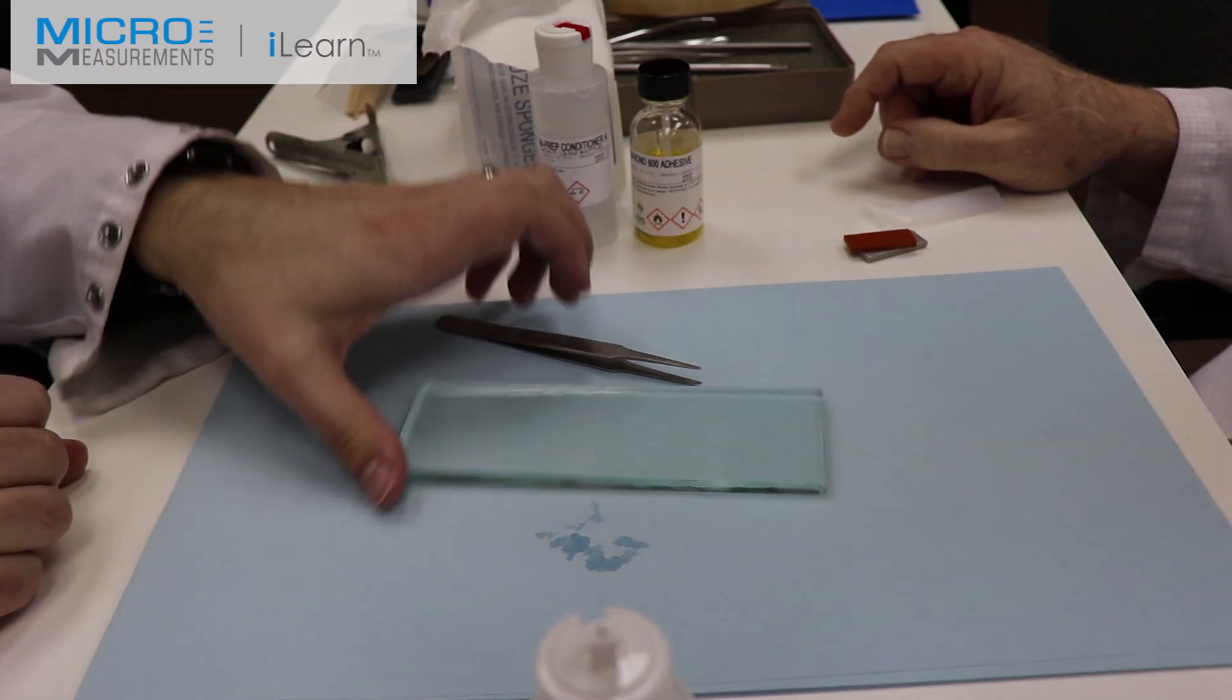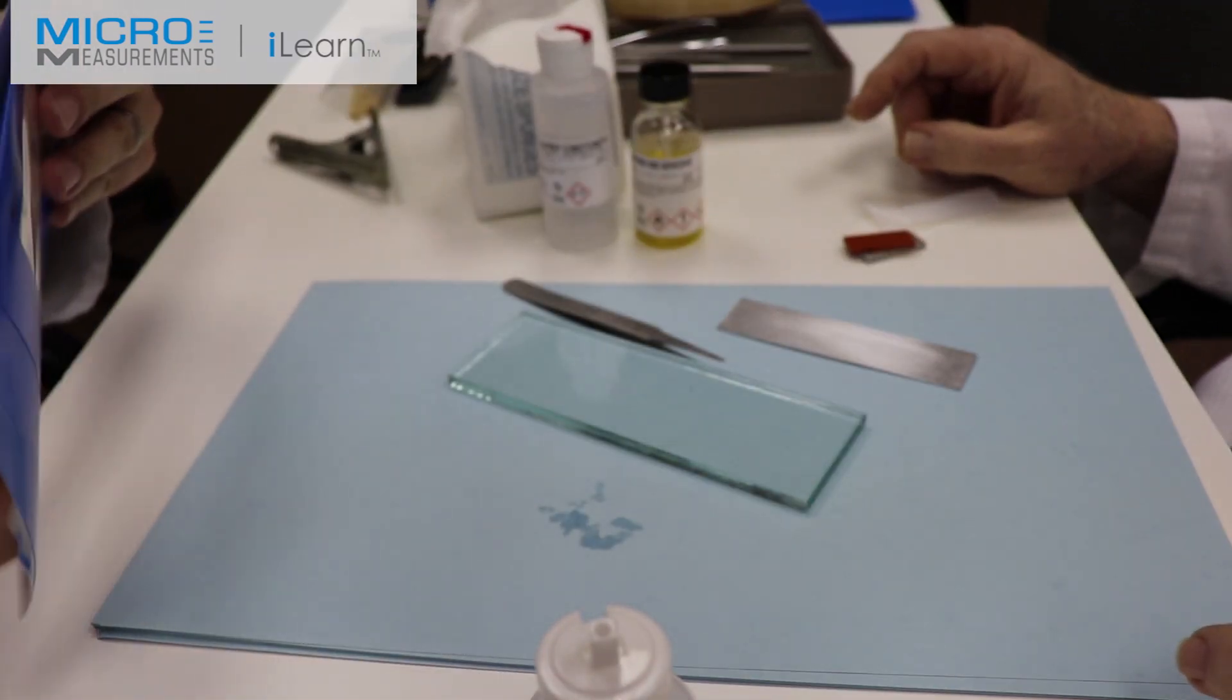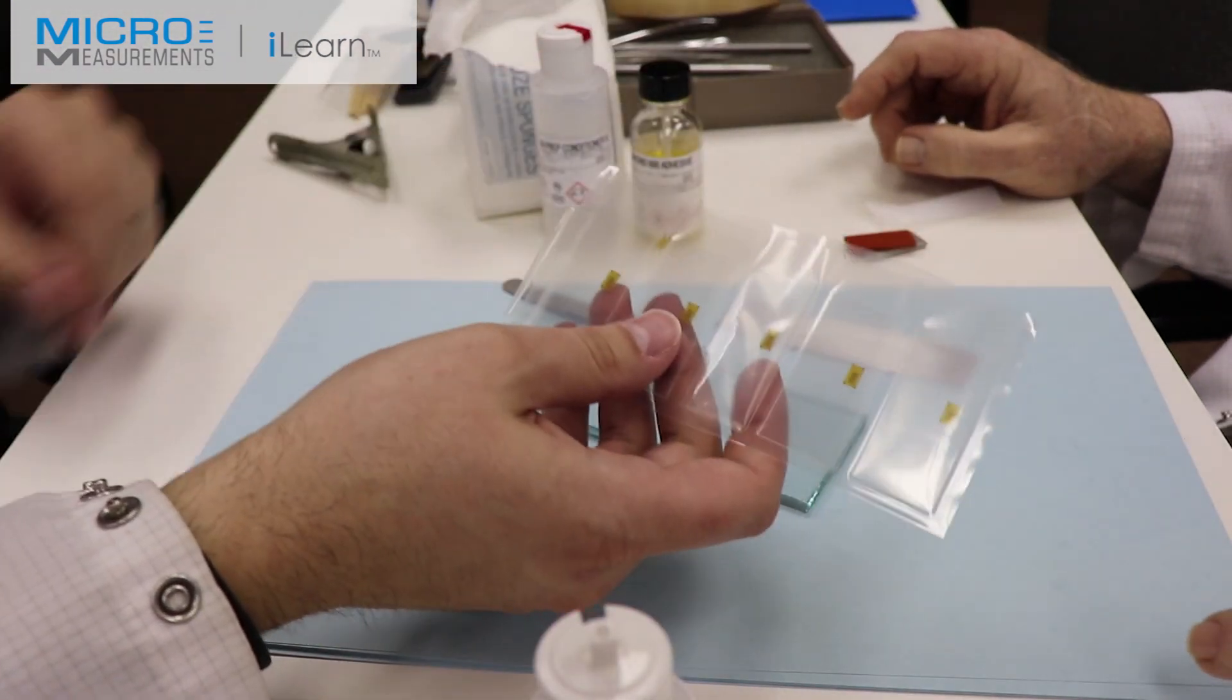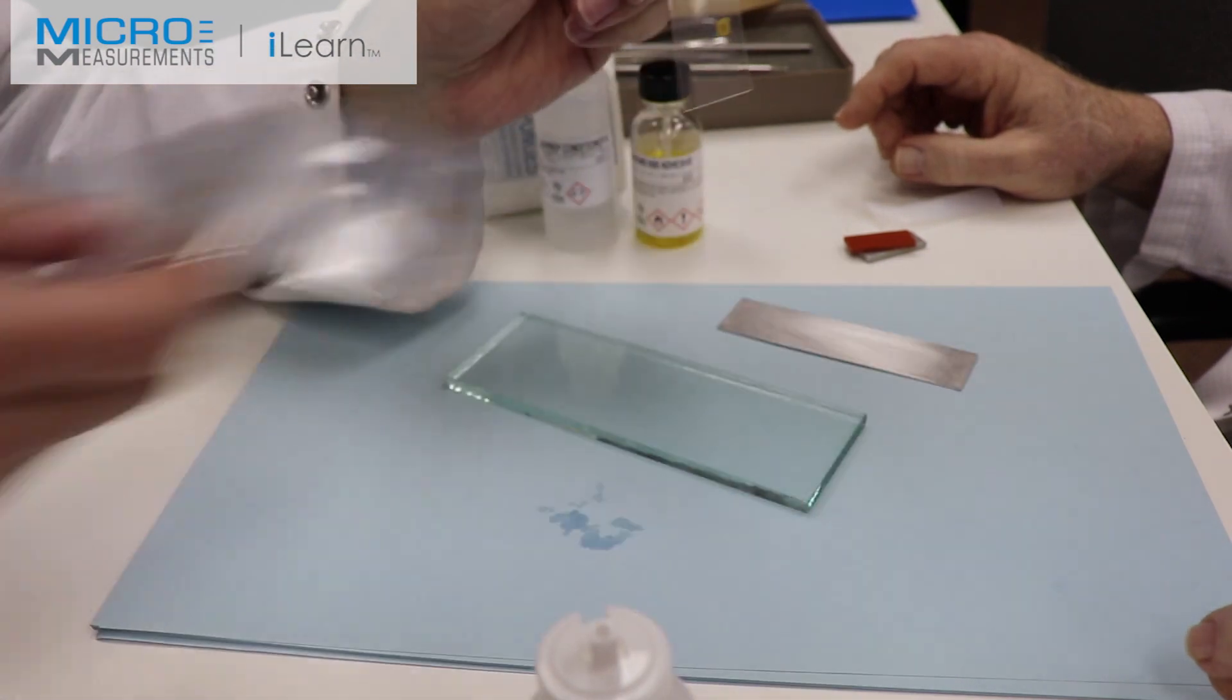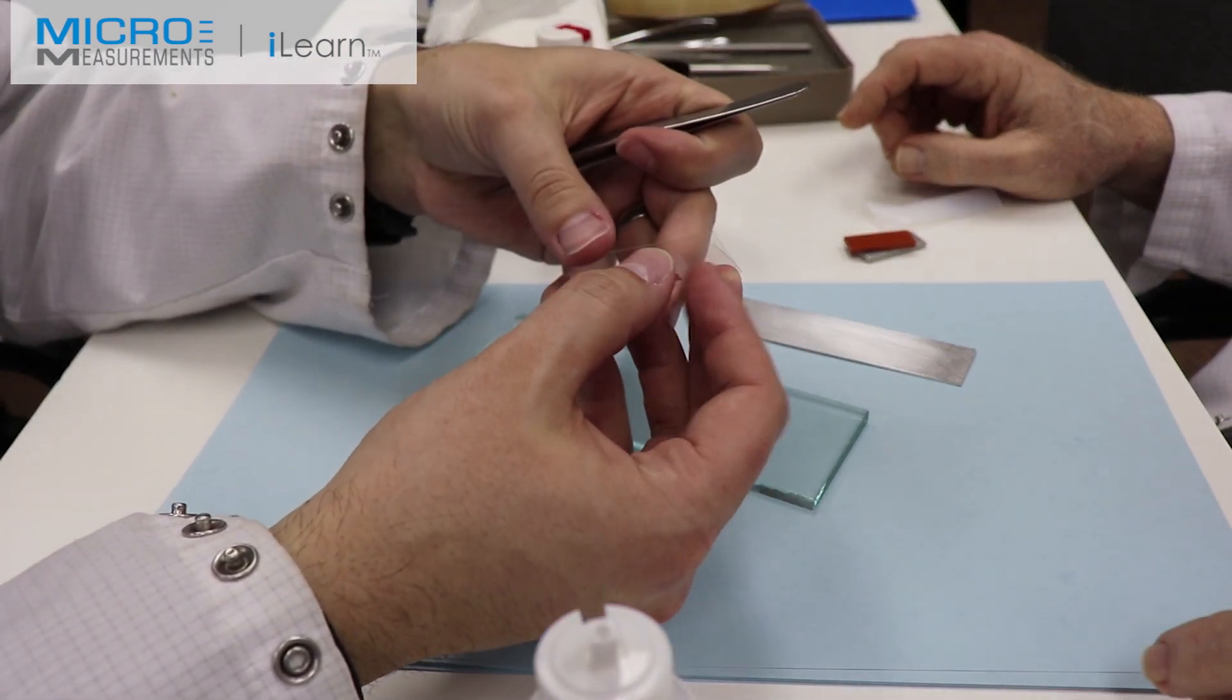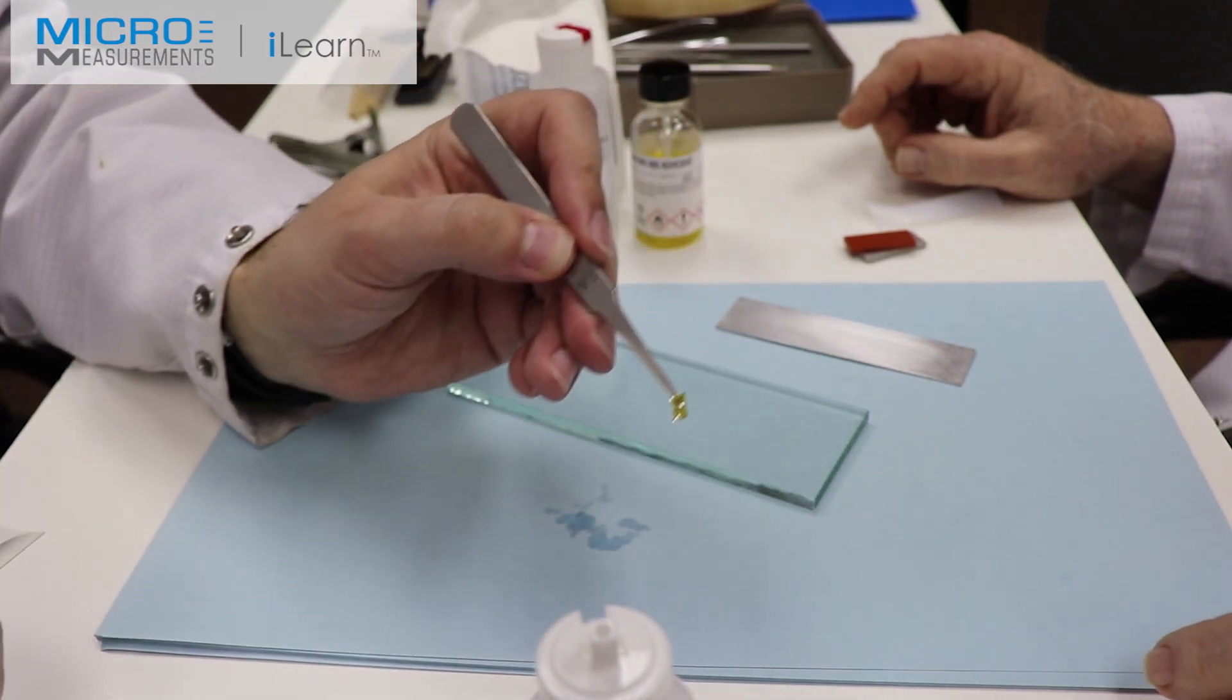Now we're going to open up the gauge package, and using our blunt nose tweezers, having pulled the gauges out of the plastic pouch, he'll splay open that acetate folder, and if you'll notice, he's going to grab the gauge by the tab end. If we grab it by the grid end, there's a possibility that we'll damage that grid during the install.